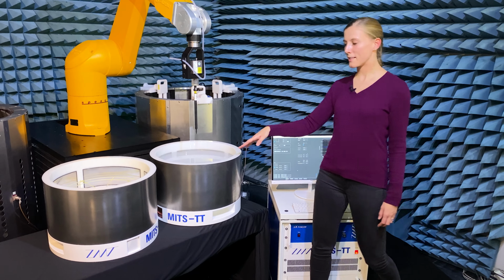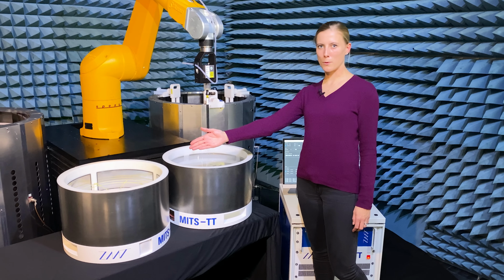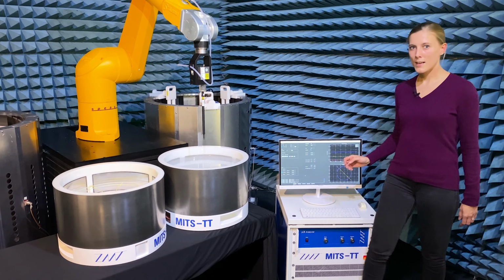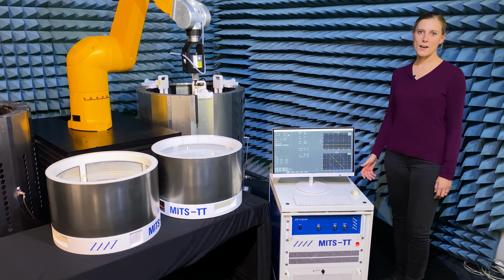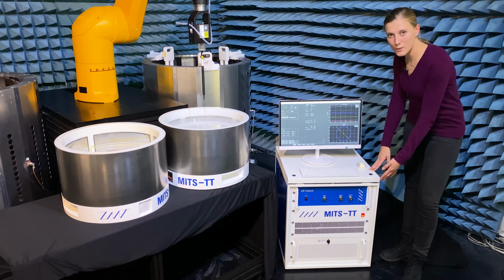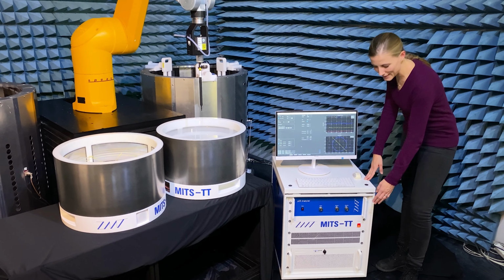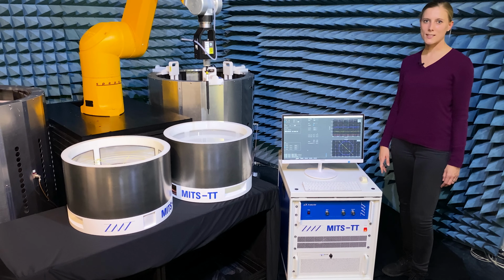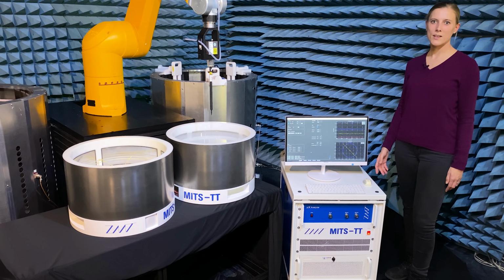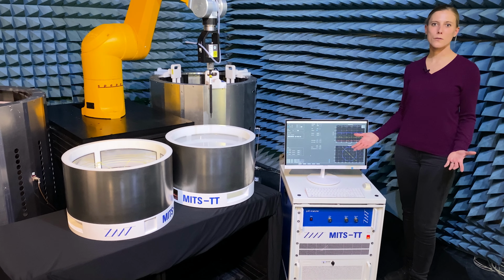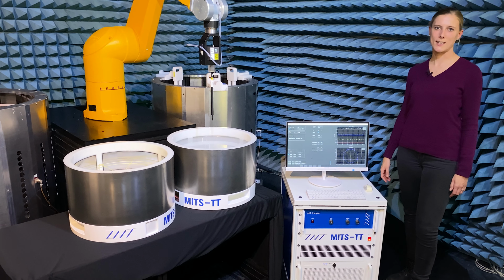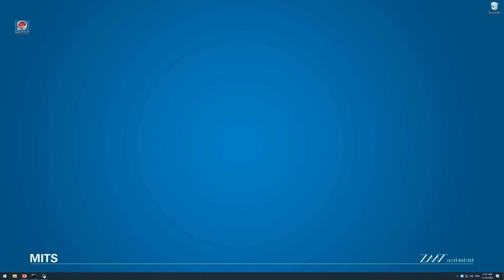We have a MITS-TableTop high permittivity and low permittivity phantom. The dual band source, the amplifiers, and the computer are all housed in this rack. And as you can see here, Zurich MedTech's piecewise excitation system fits in the same rack, so we can offer the entire workflow for RF implant safety testing here. Upon start of the software, you have to choose the operating frequency, either 64 or 128 MHz. You also need to choose which unit you are using, the HPM or the LPM.